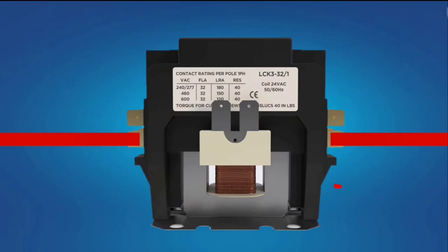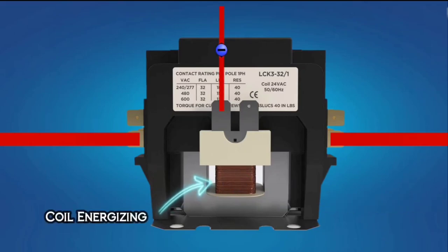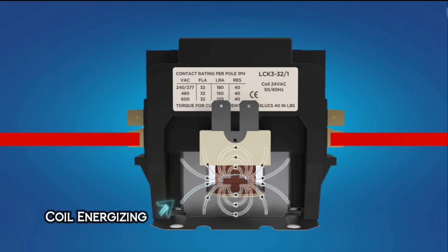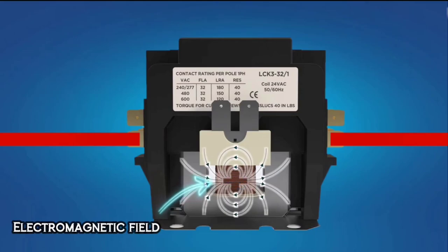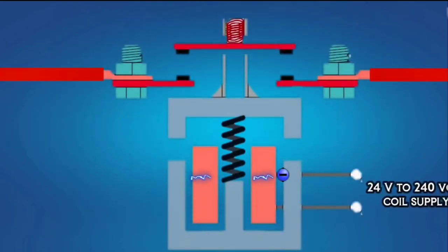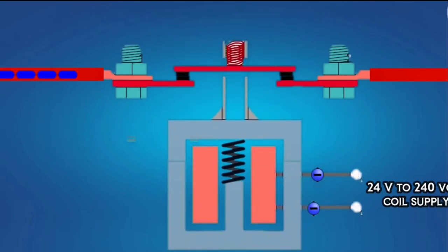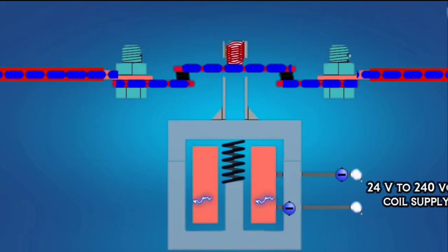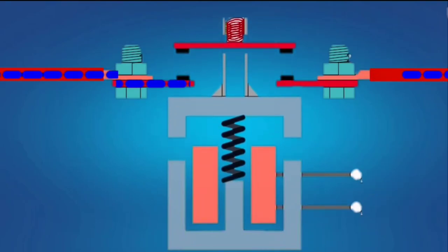A contactor has a low voltage coil. When 24-volt power is supplied to this coil, the coil energizes, and an electromagnetic field is generated in the coil. By this magnetic field, the terminal in it is attracted and connected, and the power supply will start to flow through it. When it is de-energized, the electromagnetic field will be cut, and the terminal will come back to the original position through spring force, and the power supply will be cut.